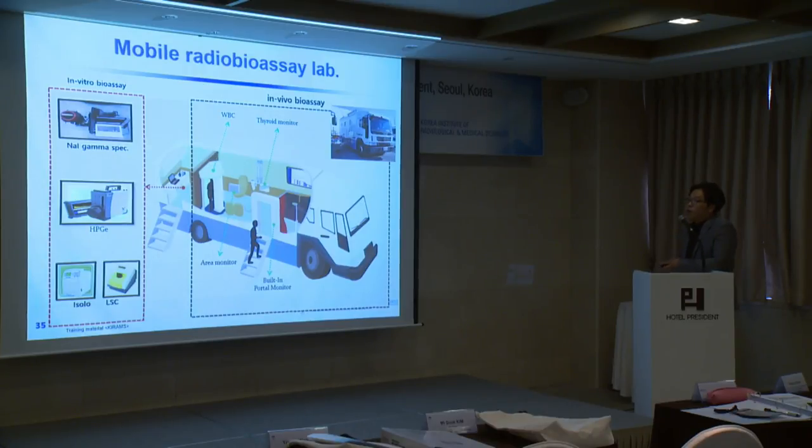As I said, KIRAMS also has opened a mobile radio bioassay lab like this. And we also have a system to respond in on-site situations. One part consists of in vivo bioassay equipment, like a whole body counter, thyroid monitor, and portal monitor, and the other consists of in vitro bioassay like a gamma spectrometry system, germanium detector, and liquid scintillation counter. So we can respond to the accident with this mobile laboratory system as soon as we can.